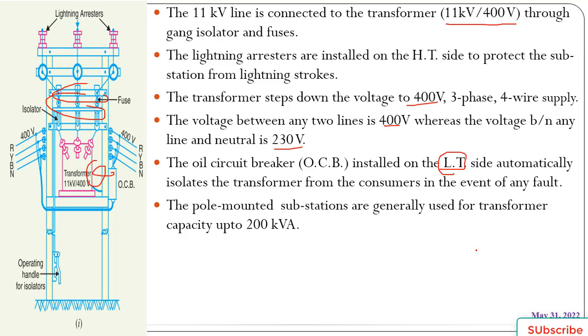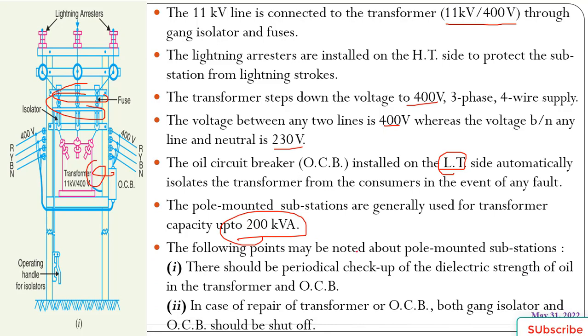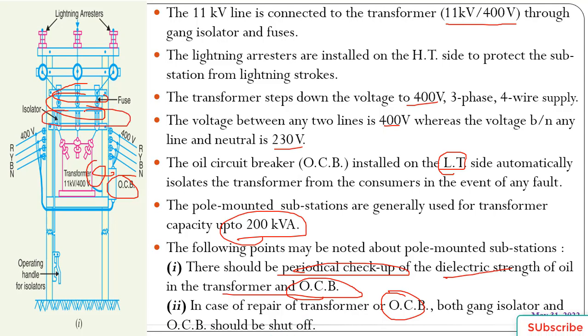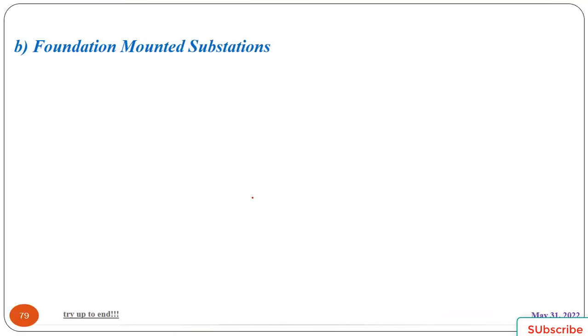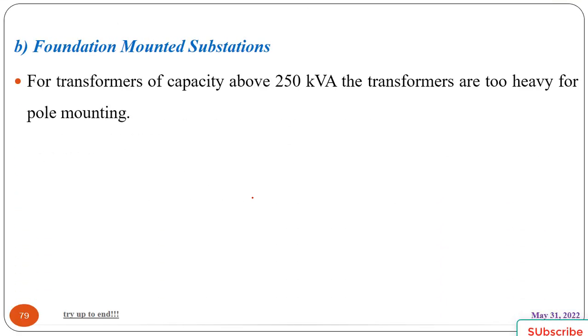The pole mounted substations are generally used for transformer capacity up to 200 kVA. The following points may be noted about the pole mounted substation. One, there should be a periodical checkup of the dielectric strength and the insulation type of oil in the transformer and oil circuit breaker. In case of repair of the transformer or oil circuit breaker, both the gang isolators and the oil circuit breaker should be shut off. The gang isolators and circuit breaker must be shut off.